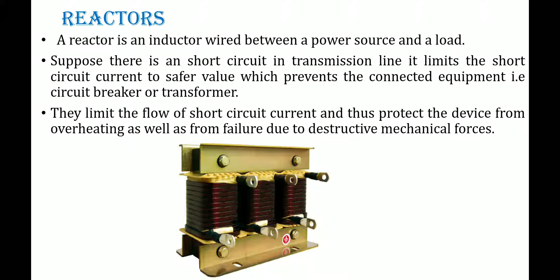Next, they limit the flow of short circuit current and thus protect the device from overheating. A short circuit means an inrush of current, and if the current is more, the temperature obviously increases. If that temperature increases beyond the limit, the insulation gets damaged. That is the reason these line reactors limit the flow of short circuit current and protect the device from overheating as well as from failure due to destructive mechanical forces. These are the reactors used in transmission lines.